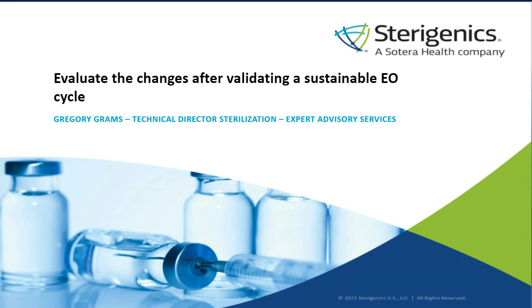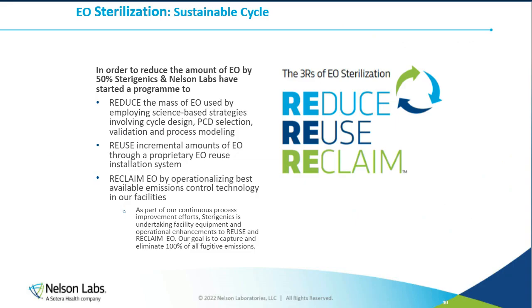And first of all, the first question that I would have is, why would I validate a new cycle? Because if I have a legacy cycle that is working fine for a long time, I don't see a reason why I would change. In 2019, the FDA has opened the EO Challenge 1 and 2, and EO Challenge number 2 was really asking the sterilization contractors as well as manufacturers to see how we could have a sustainable ethylene oxide sterilization over time, because it is a harmful gas. It is well efficient and effective for sterilization, but control for environmental consideration is a bit more complex.